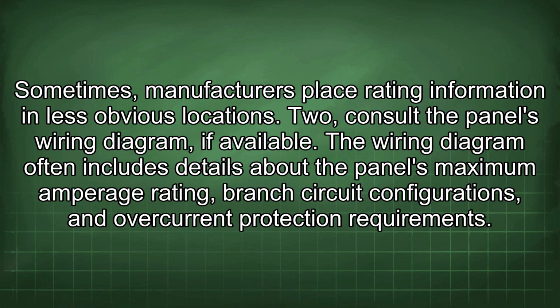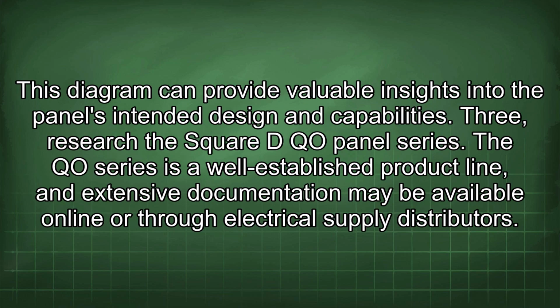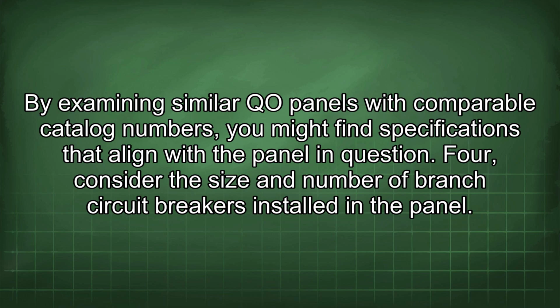2. Consult the panel's wiring diagram, if available. The wiring diagram often includes details about the panel's maximum amperage rating, branch circuit configurations, and overcurrent protection requirements. This diagram can provide valuable insights into the panel's intended design and capabilities. 3. Research the Square D QO panel series. The QO series is a well-established product line, and extensive documentation may be available online or through electrical supply distributors. By examining similar QO panels with comparable catalog numbers, you might find specifications that align with the panel in question.